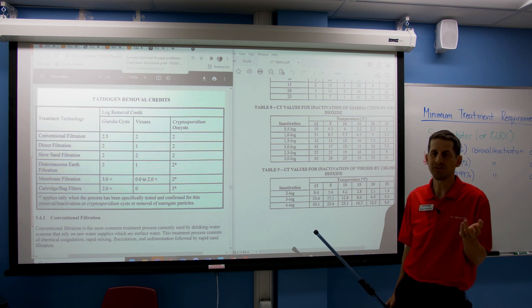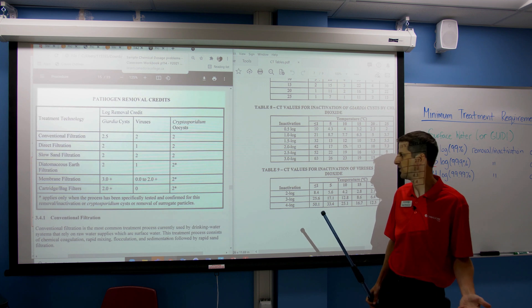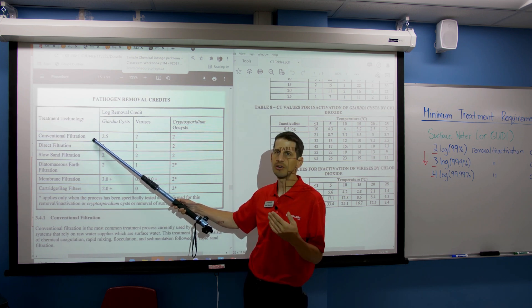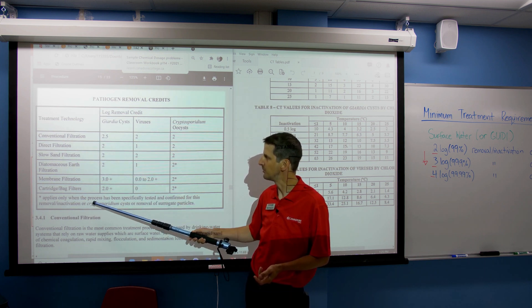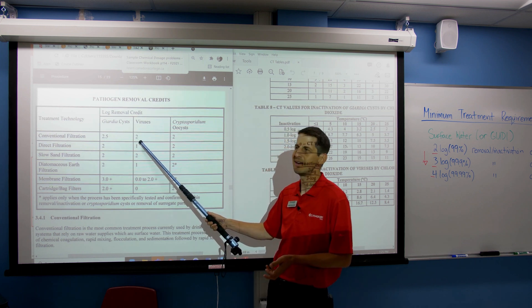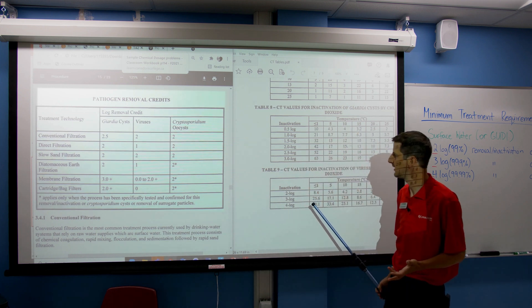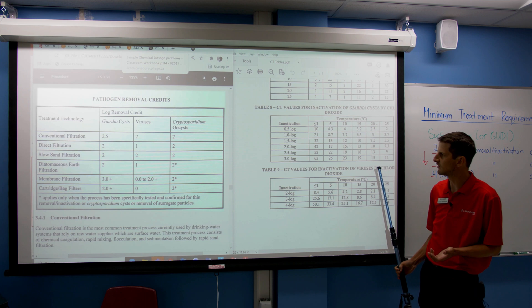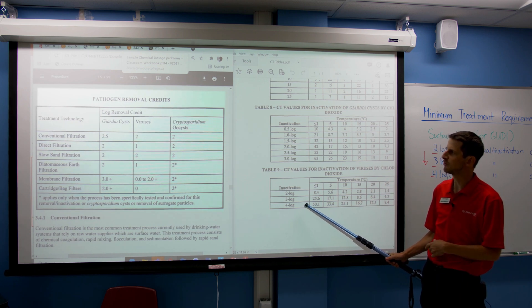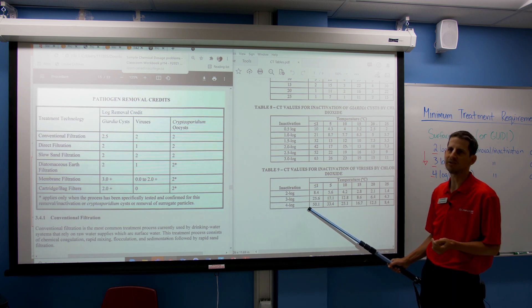But if you're doing chemically assisted filtration — if you're coagulating and filtering — you might be catching some of these things. So the question is: how much less than four log can we get away with? Looking at conventional filtration, which is coagulation and filtration, we get a credit of two — these are log removal credits. So for doing regular treatment, we're already removing two log of viruses. When we go back to the CT table, we only need to look at the two log value, not the four, because we're already getting a credit for two from conventional filtration. Whenever you're trying to meet your 2-3-4 CGV requirements, make sure you check the procedure for disinfection of drinking water to find out how much credit you get, so you know what value to use in your CT calculation.